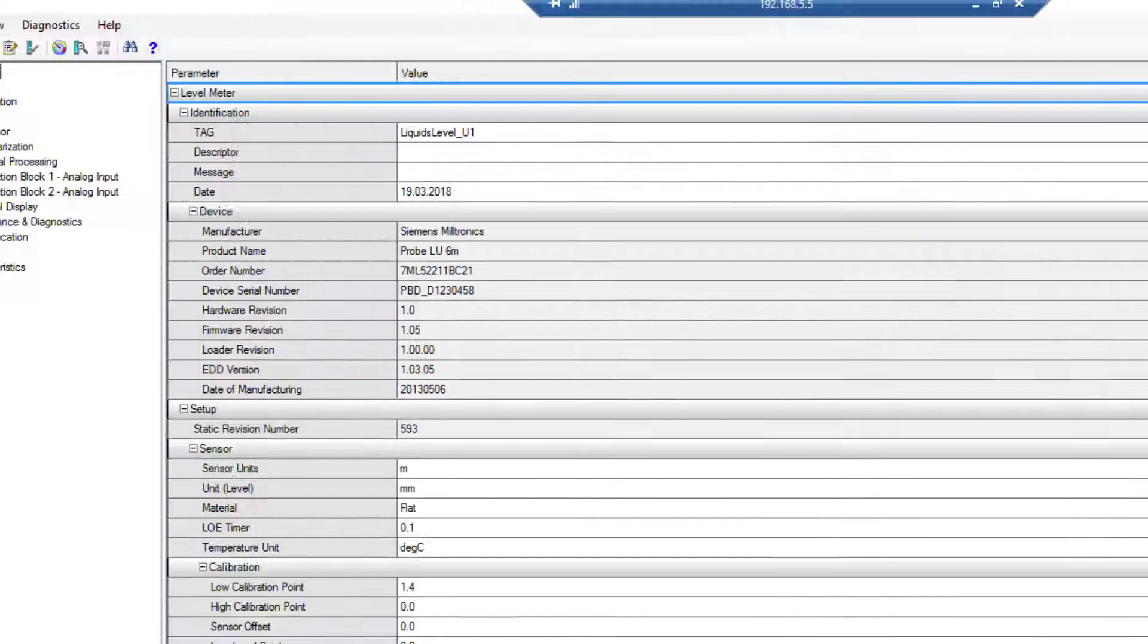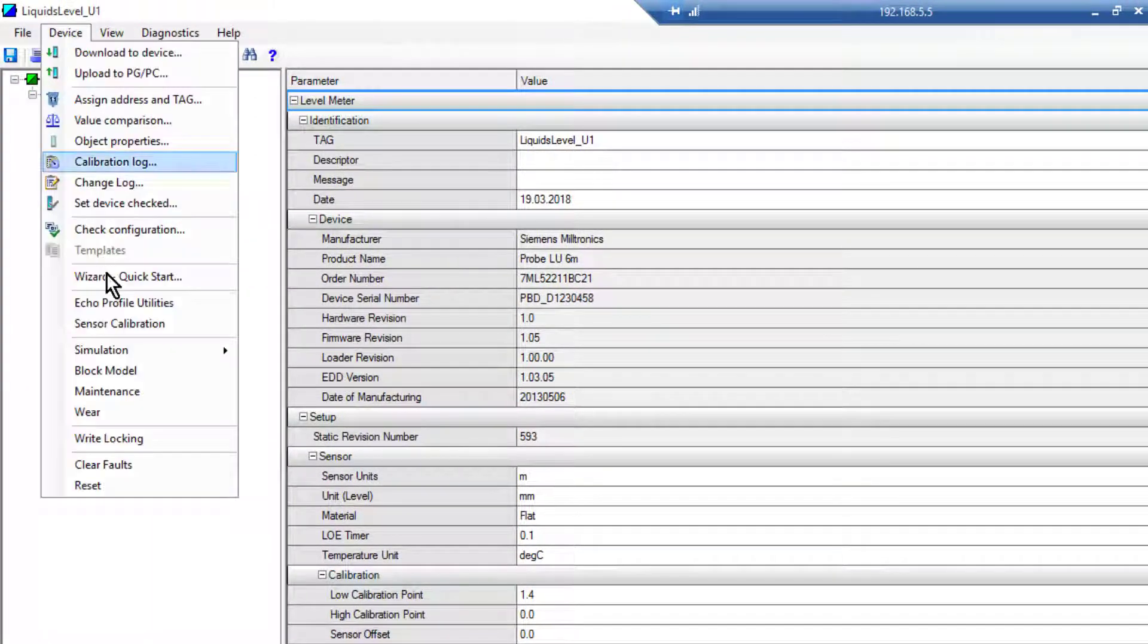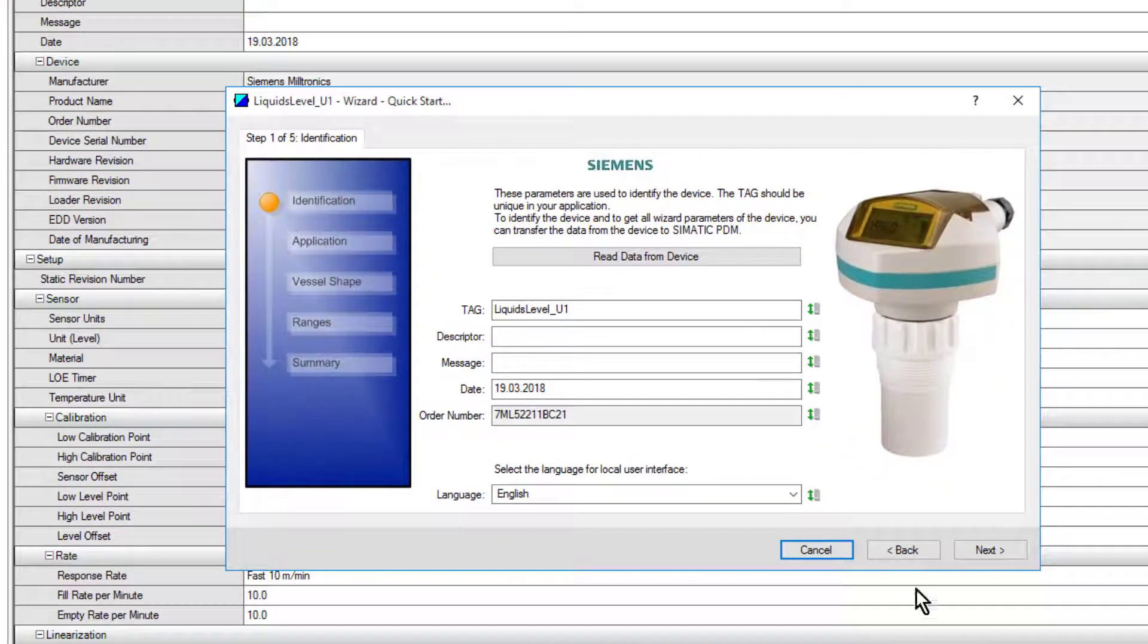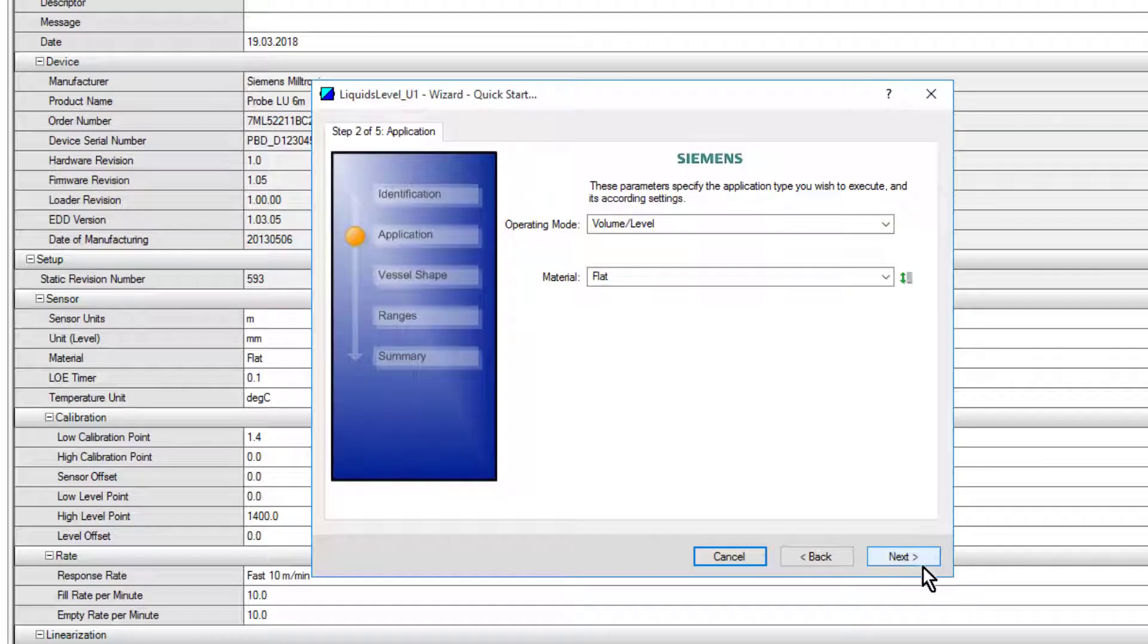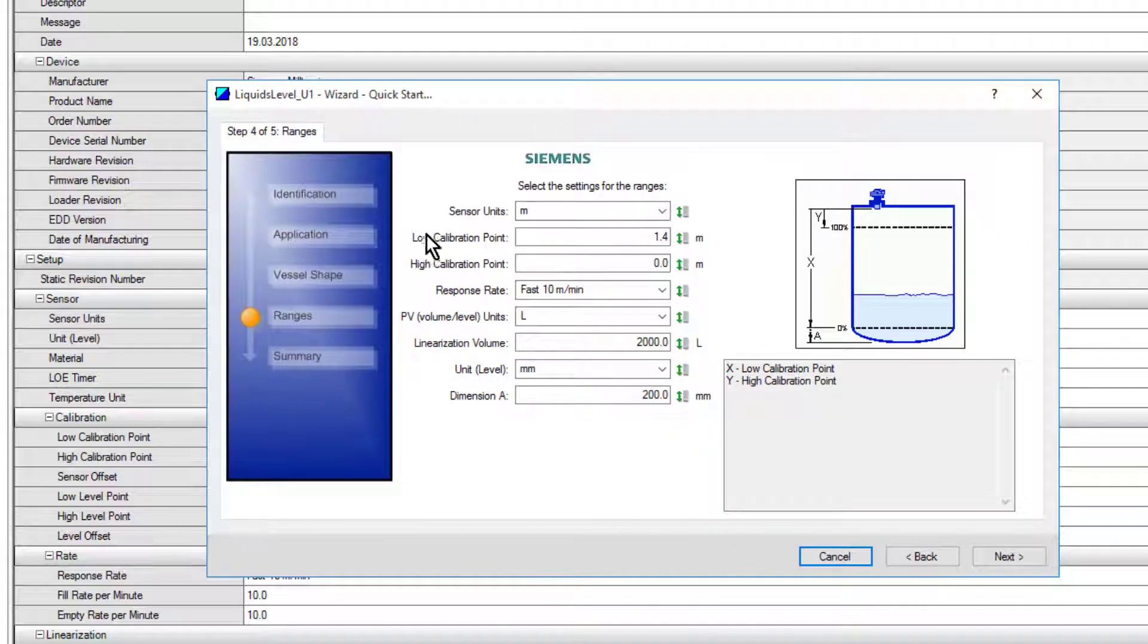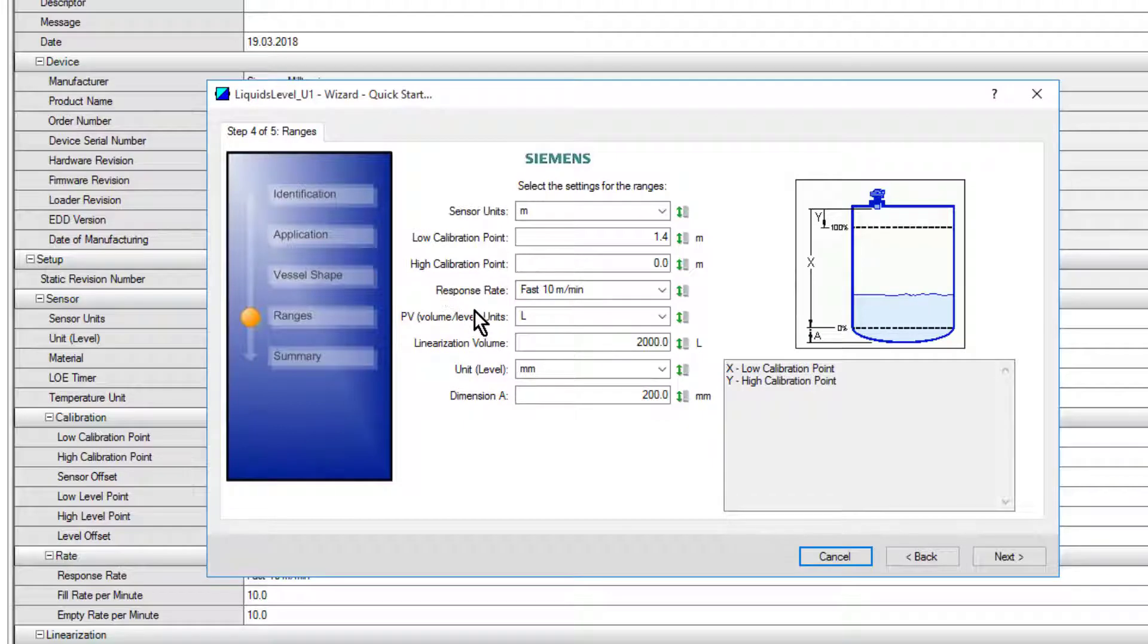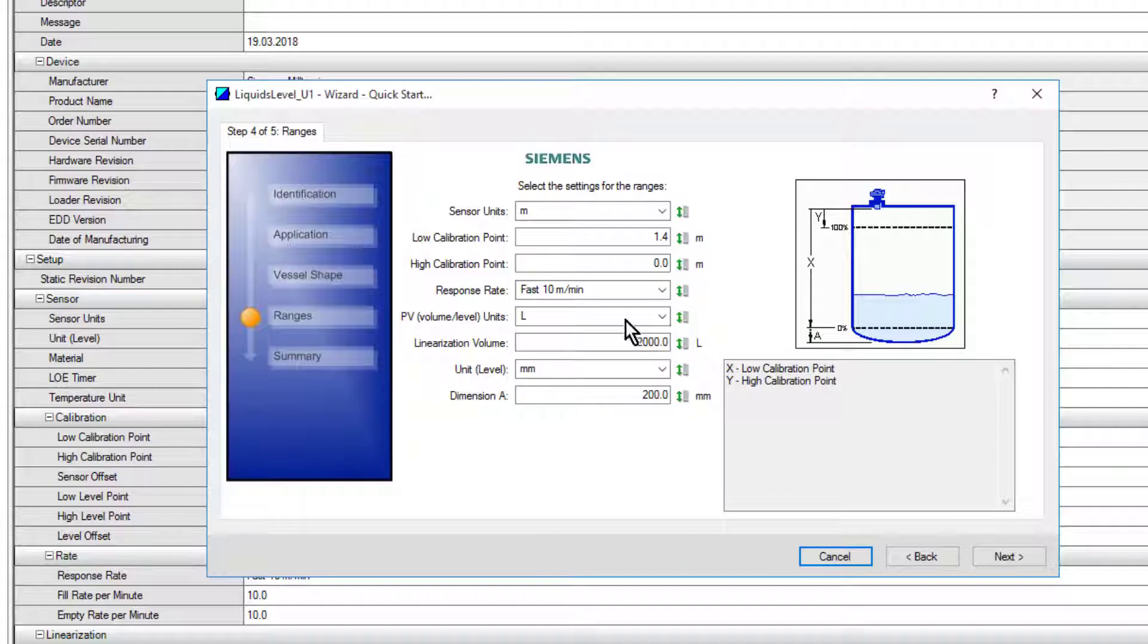You'll see those highlighted in the file structure. If I had to program this from scratch on this Siemens device, I could use the quick start wizard. You can do level or volume, parabolic end, put in the dimensions, your calibration points in level, your X and Y points, the high calibration point, the low calibration point, what you want the output to read in, and what the volume is at your level of 1.4 meters.